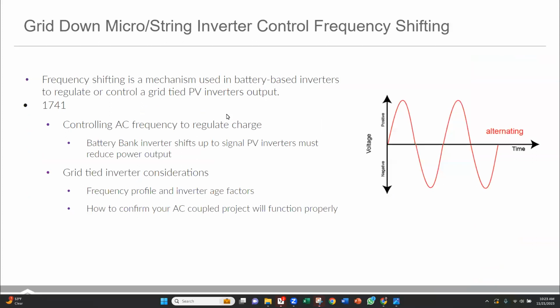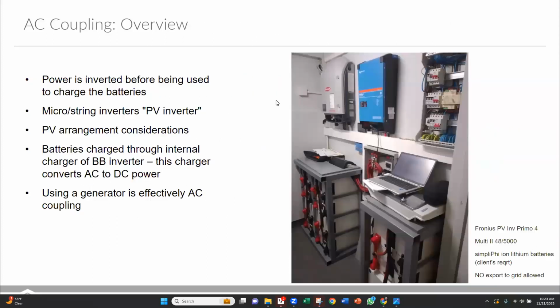So Nathan, let's go back one slide. I want to make sure we're all understanding why we would even do AC coupling. As somebody who's coming from the old off-grid days, DC coupling always made sense, right? You lose efficiency, you lose something every time you switch from AC to DC. So taking DC out of the panels, DC into the batteries, and only when we need to power loads do we switch it. What I imagine in this picture here, and I don't know the exact details, is that at some point they only had that grid-tied Fronius sitting there. And we know, based on the anti-islanding rules, that if power went out, that Fronius is automatically going to shut itself off.